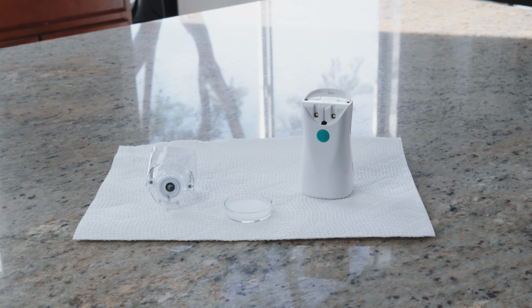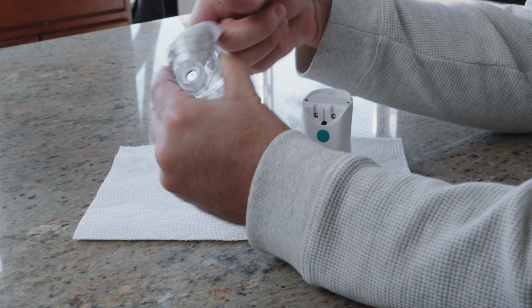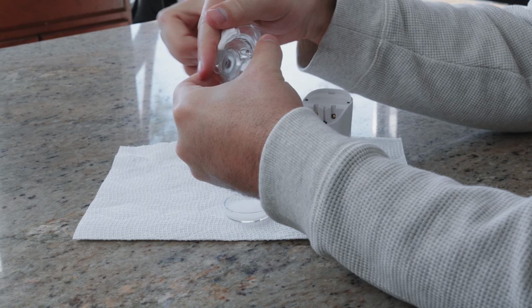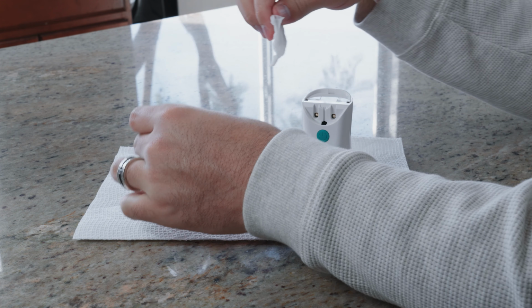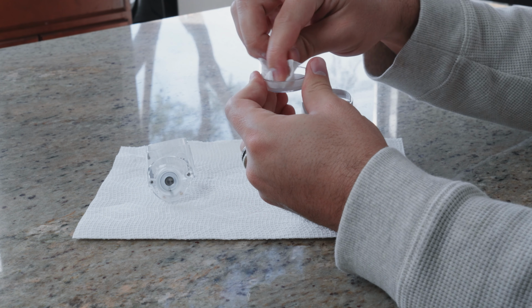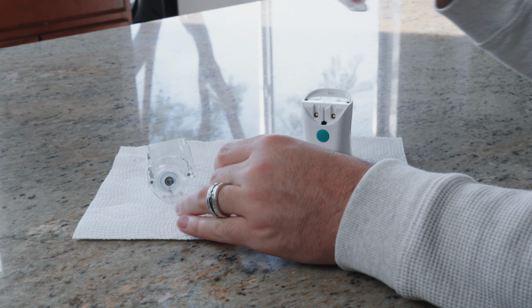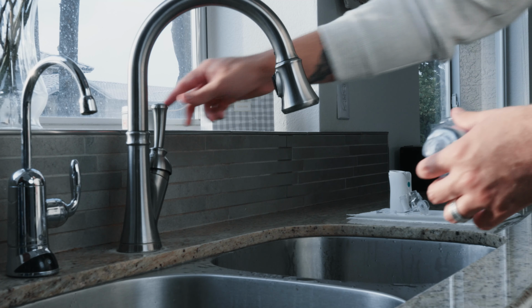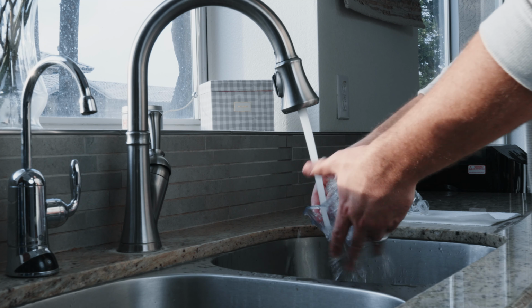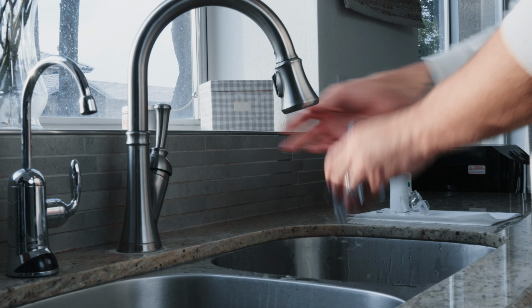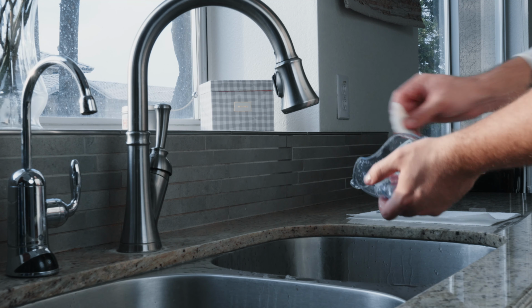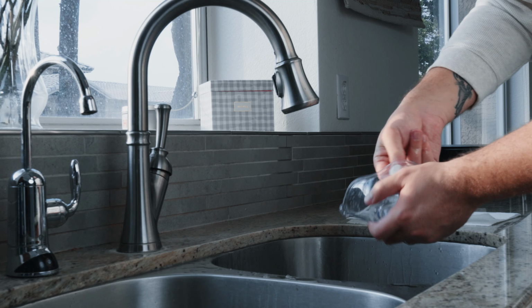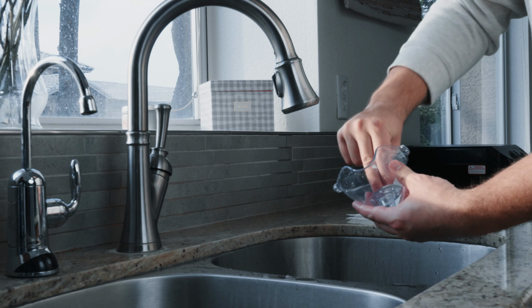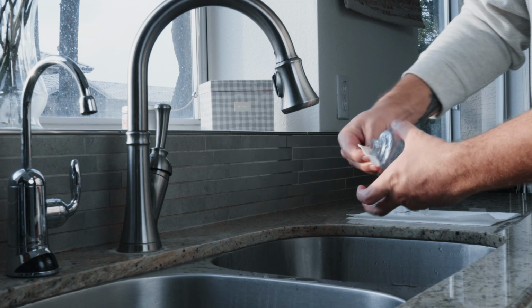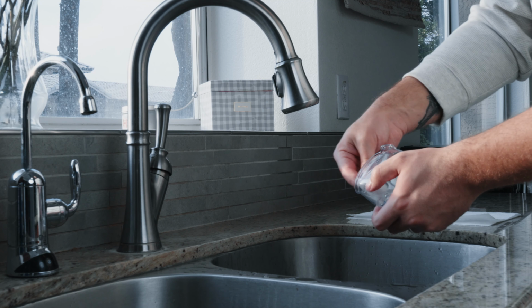Detach the reservoir from the main unit and take off the lid. Using a medical-grade alcohol towelette, wipe the surface of the reservoir starting from the inside of the cup to the outside of the cup and mouthpiece connector. Make sure not to touch the metal mesh plate in this process. To clean the mask or mouthpiece, simply rinse with water and wipe with a medical-grade alcohol towelette. Leave all of the pieces in a well-ventilated area to dry completely before storing. Do not wash the main unit. Simply wipe with a soft cloth or alcohol wipe.